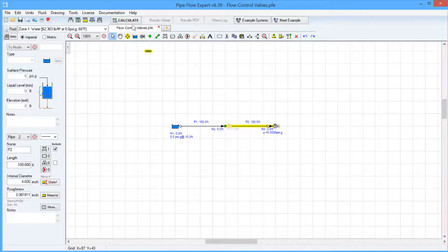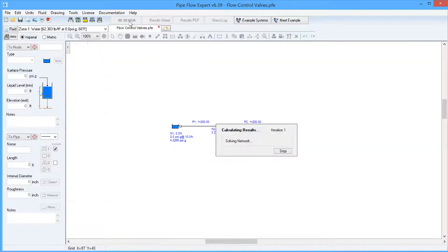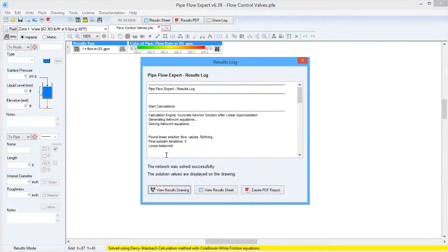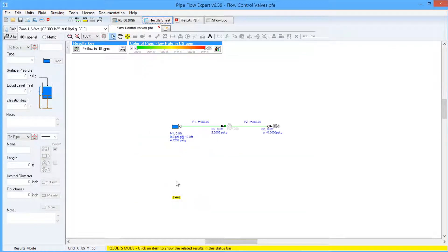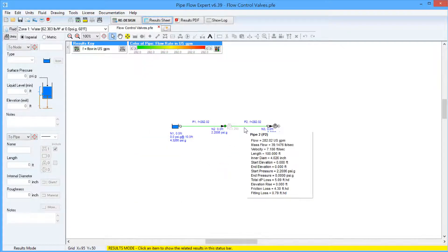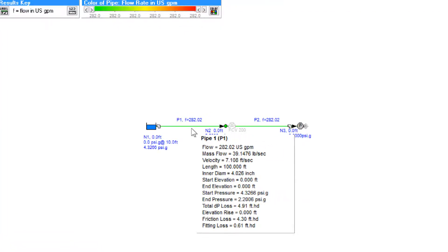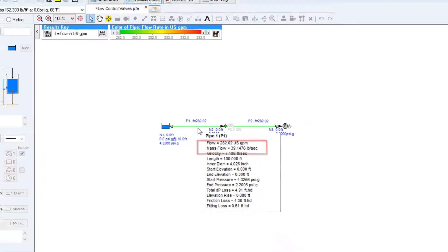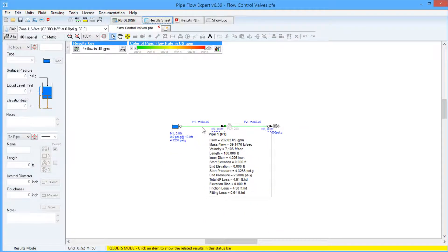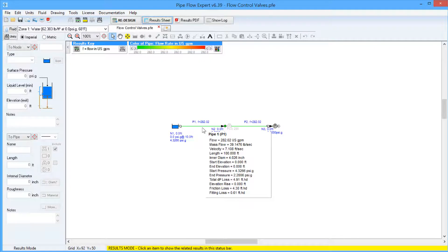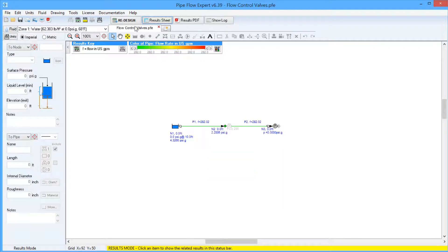So if we recalculate this system now, view the results drawing, and hover over the pipes in the system, we can see that we have now an increased flow of just over 282 US gallons per minute, which is because the flow control valve is not controlling the flow anymore.